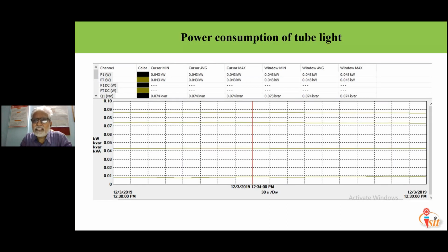Now here is what we did: the reading we took for the tube light at one of the colleges. This is the data, the report of the power analyzer. That tube light is called a 36 watt tube light. Generally we always say it is a 40 watt tube light, but actually it is 36 watt. However, the actual reading shows it is drawing 43 watts.